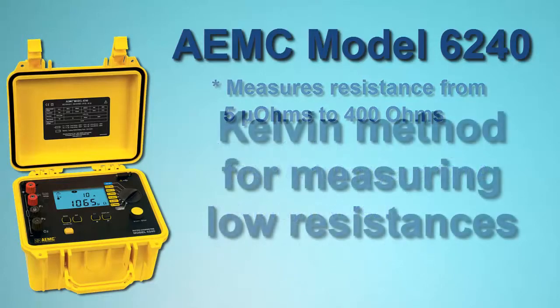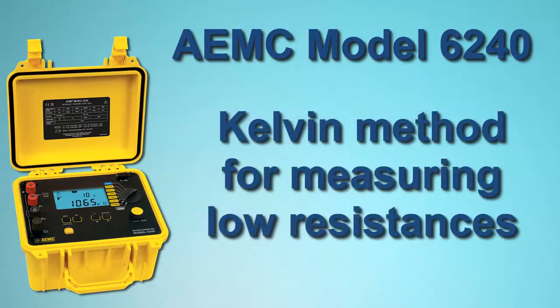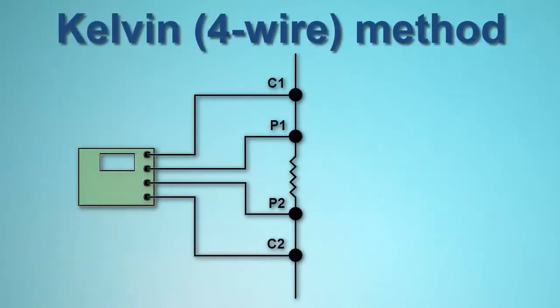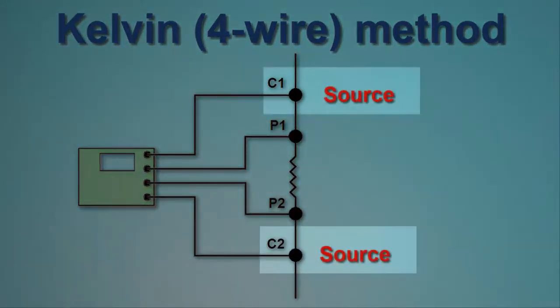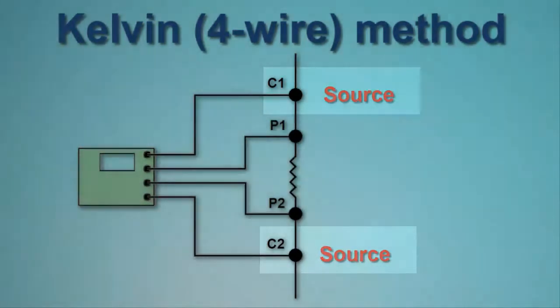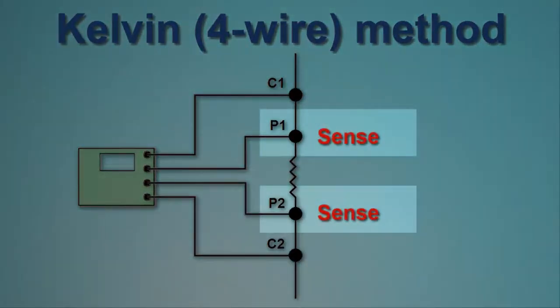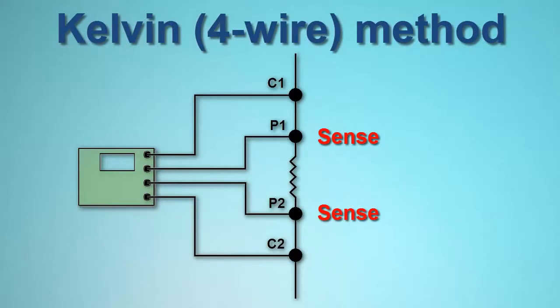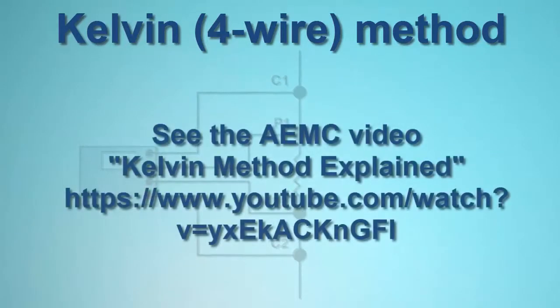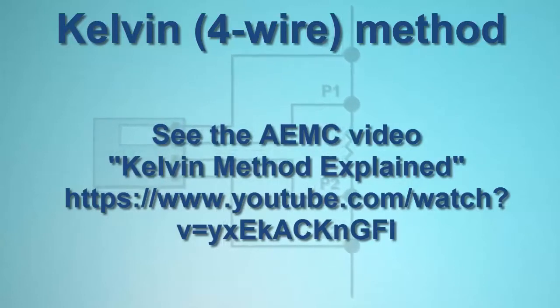The Model 6240 employs the Kelvin testing method to measure very low resistances to within a quarter of a percent accuracy. Kelvin testing uses two separate pairs of leads. One pair, called the source leads, provide a known quantity of constant current. The second pair, called the sense leads, measures voltage. There is virtually no current flowing through the sense leads. Nearly all the current flows through the source leads. This allows for a high level of measurement sensitivity and accuracy when the load under test is of low resistance.